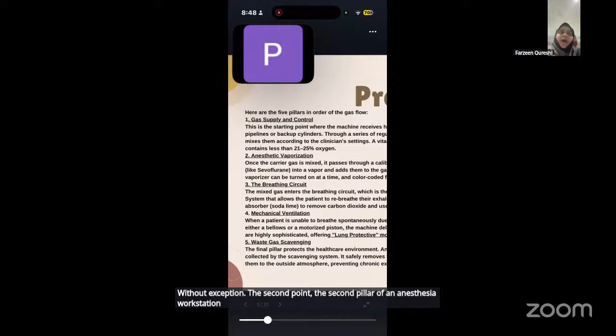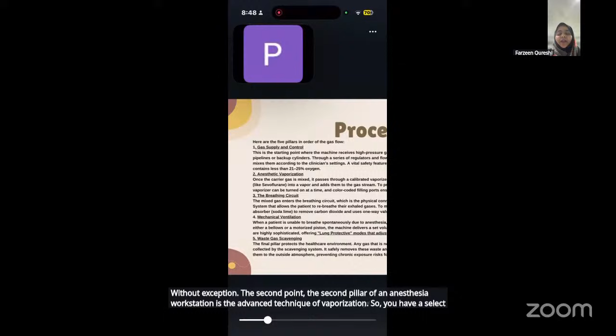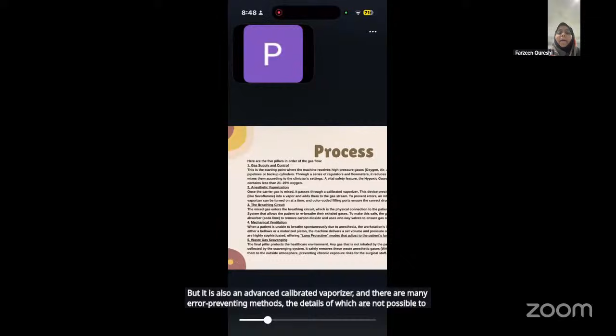The second pillar of an anesthesia workstation is the advanced technique of vaporization. So you have a Selectatec vaporizer. Nowadays, you have the desflurane vaporizer, which is not a Selectatec vaporizer, but it is also an advanced calibrated vaporizer. And there are many error-preventing methods, the details of which it is not possible to touch on right now. But the vaporizers have advanced to the precision that 0.01 ml of sevoflurane can be measured, calculated, and even billed to each patient separately.